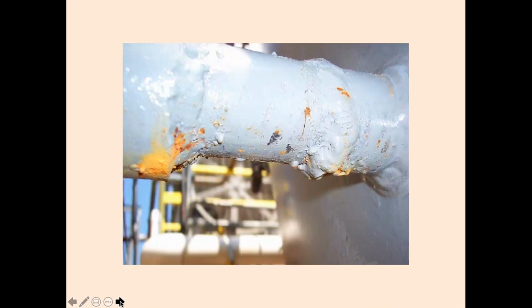This is a pipeline, an insulated pipeline. You will see this is a regular pipeline. The insulation has been made. A pipe which is visible to the naked eye, yes, you can replace it, but insulated pipes cannot. You do not know what has happened inside. The moisture has seeped in and the breakdown, the accident, has taken place because of improper insulation.